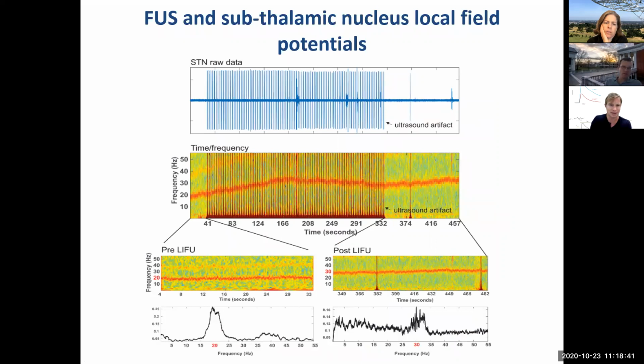The other thing we can look at is the local field potential activity. Here's our raw data up here. You can see the ultrasound artifact. Then if we do a simple wavelet convolution, you can see the strong power at 20 Hertz. This is quite common in these patients: the activity of the STN has strong power in this beta range. While we turned the ultrasound on, we saw a shifting of this power to roughly 30 Hertz, and once we turned the ultrasound off, in this case, it stayed elevated. We've blown up the pre and the post here, showing the power. Here's an FFT of this power over time, showing that it did change from 20 Hertz at baseline to 30 Hertz after ultrasound.